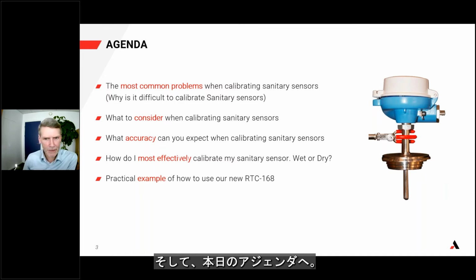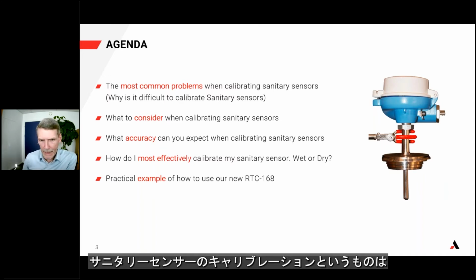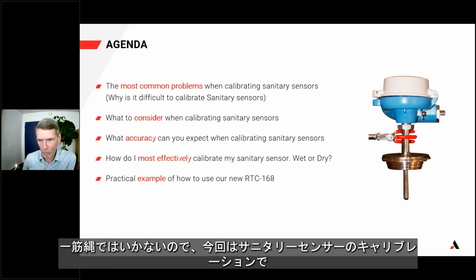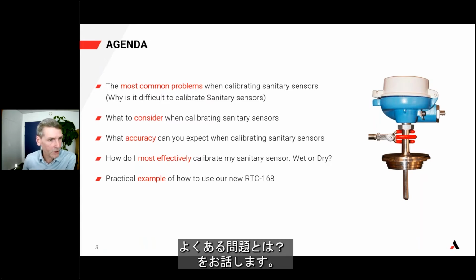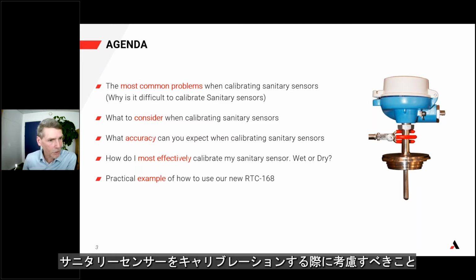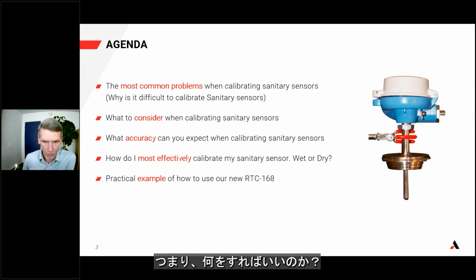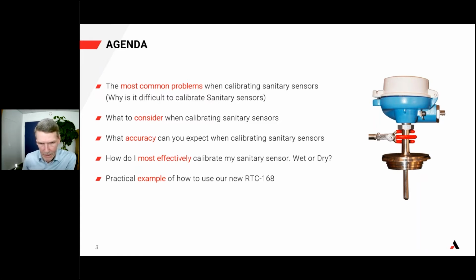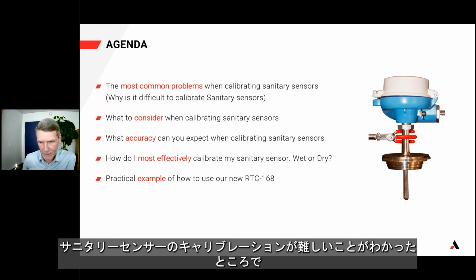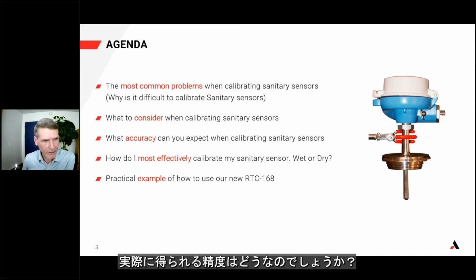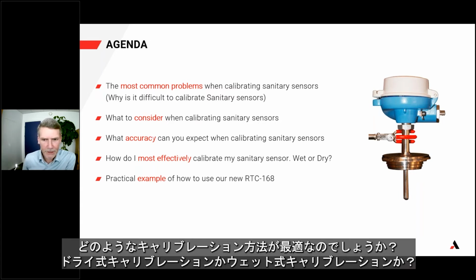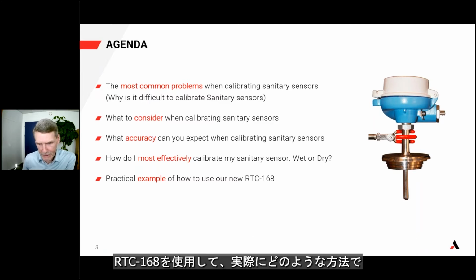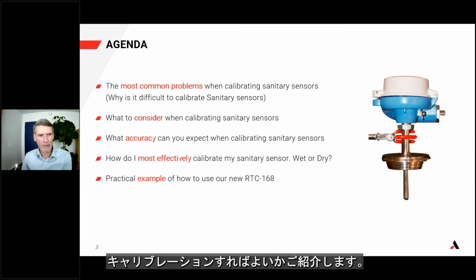And now to the agenda for today. Calibrating sanitary sensors is not a straightforward calibration, so I will discuss what the most common problems are when calibrating sanitary sensors, what to consider when calibrating sanitary sensors, or in other words, what shall I do to perform the best possible calibration? Now that we know that it's difficult to calibrate sanitary sensors, what does that mean for the accuracy we can actually obtain? What calibration method would be the best to use, wet or dry calibration? We will show a practical example of how to use the RTC168.